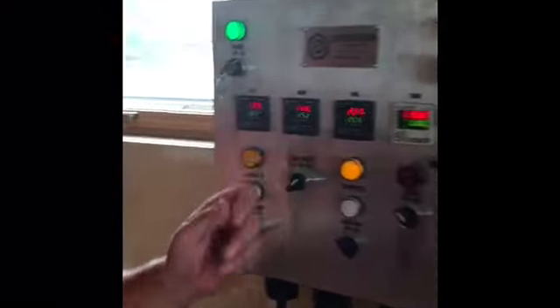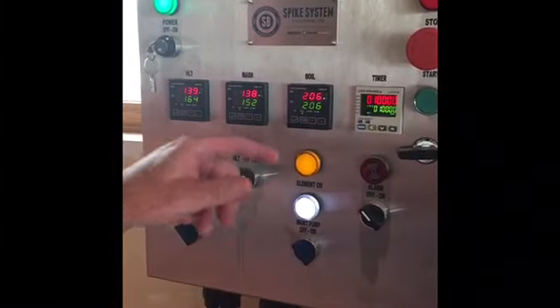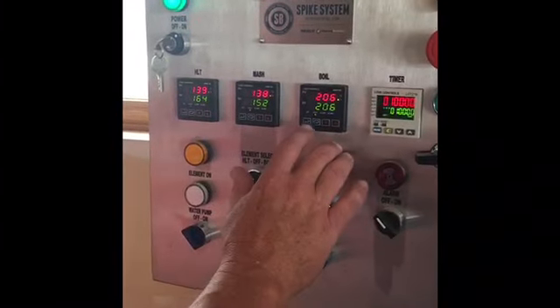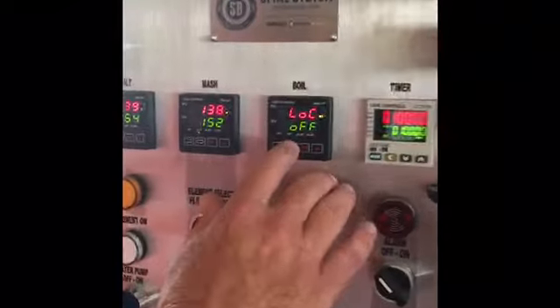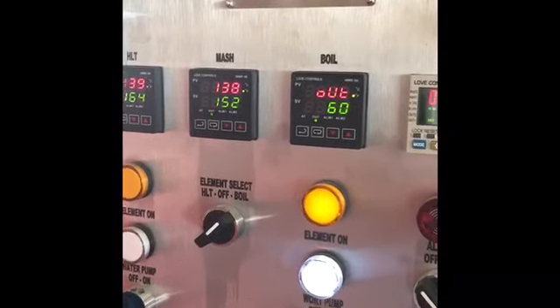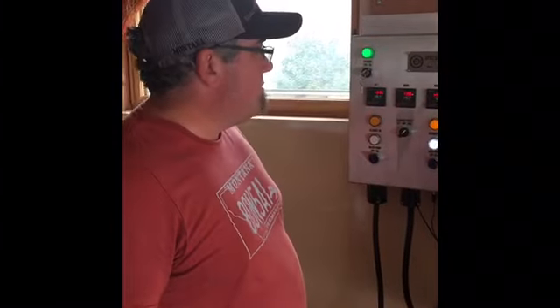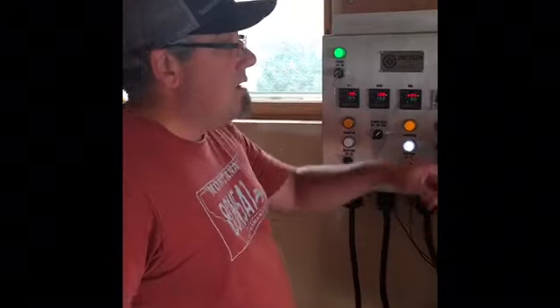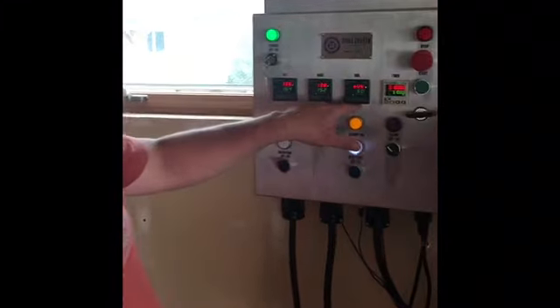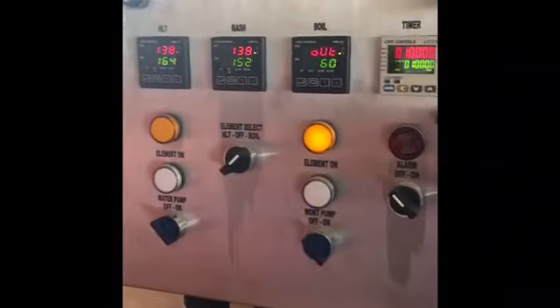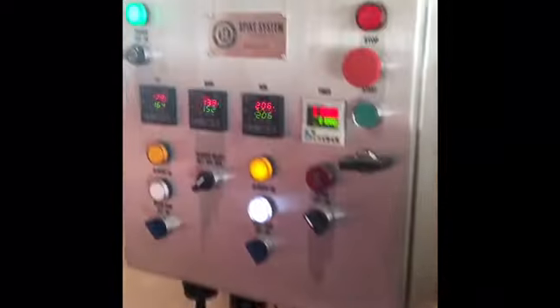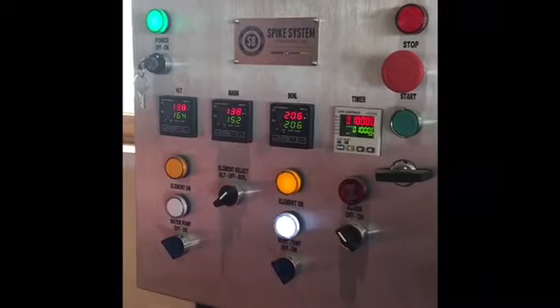One thing with this system is that the boil burner is a little different, in that it's a percentage of the output of the burner. We used about 70% of the burner, meaning it's on 70% of the time. Now we've got it down to about 60%, and that's given us a nice little rolling boil. Got us up to our 206 where we're boiling right now.